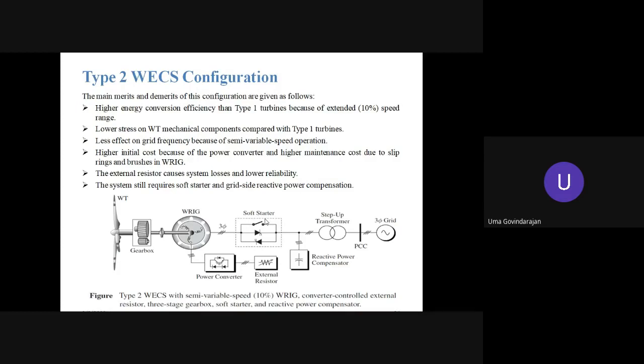Okay, it also works above the synchronous speed, but 10% speed variation is allowed. Another important point is, except in type 1 where we have SCIG, here we have the wound rotor. Here rotor power is also available. When the wound rotor induction generator operates above the synchronous speed, and type 2 operation is only above the synchronous speed, the rotor slip power is conditioned and fed into the external resistor. Or you can connect some heating type of loads here, so that power loss, instead of dissipating in a resistor, can be converted into useful energy.